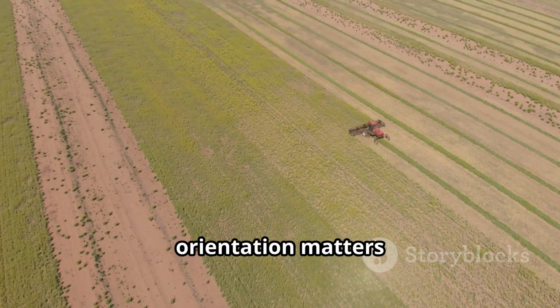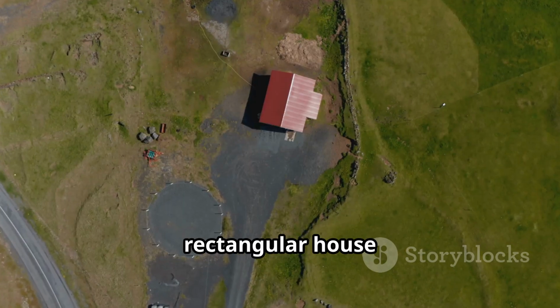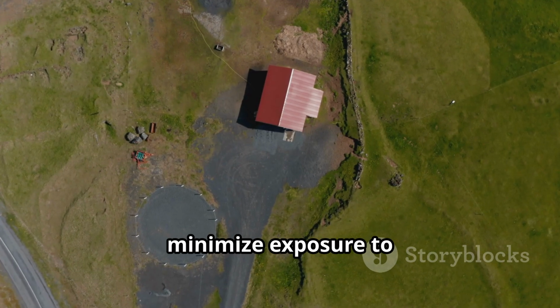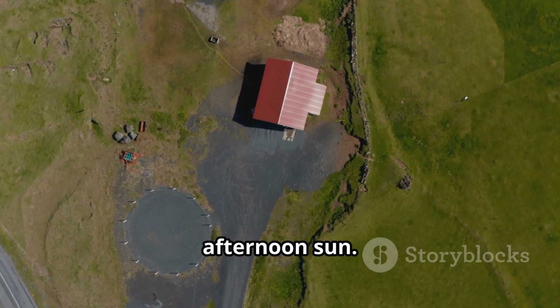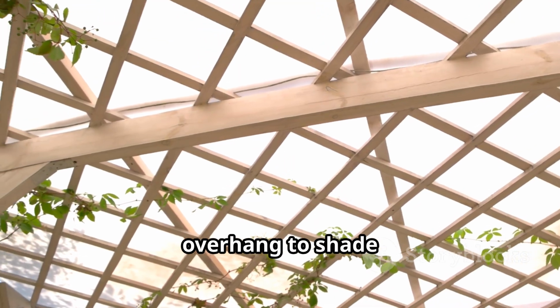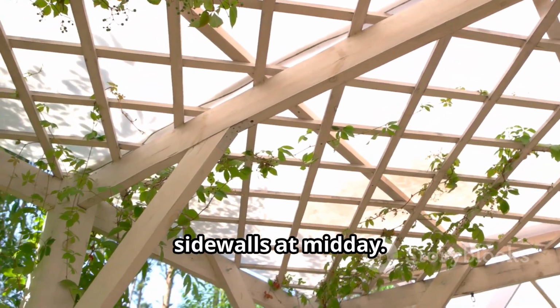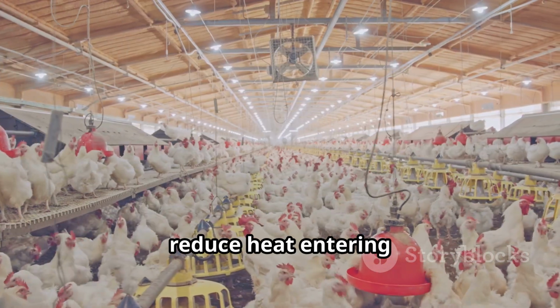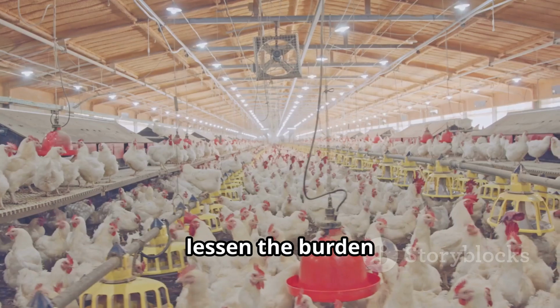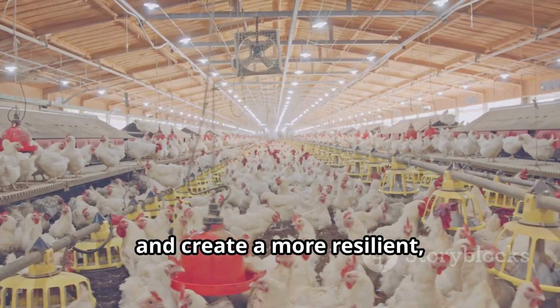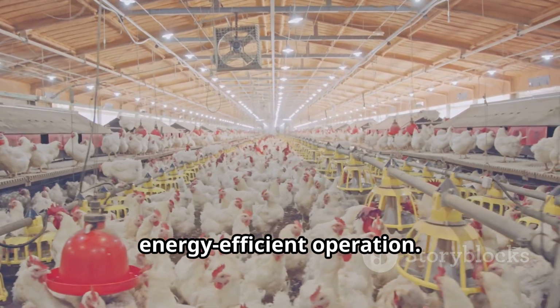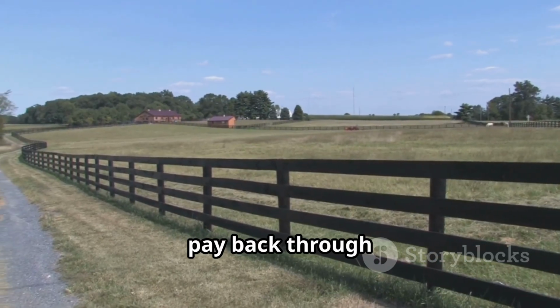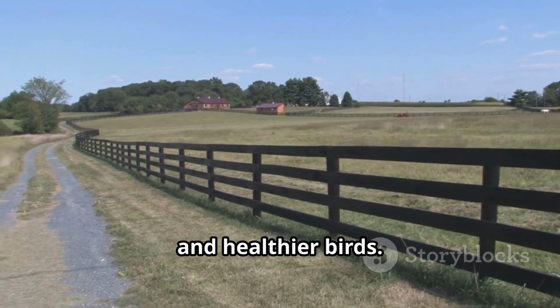Building orientation matters for new construction. Orient a rectangular house east-west to minimize exposure to intense morning and afternoon sun, and add adequate roof overhang to shade sidewalls at midday. These passive design elements reduce heat entering the building, lessen the burden on active cooling systems, and create a more resilient, energy-efficient operation.